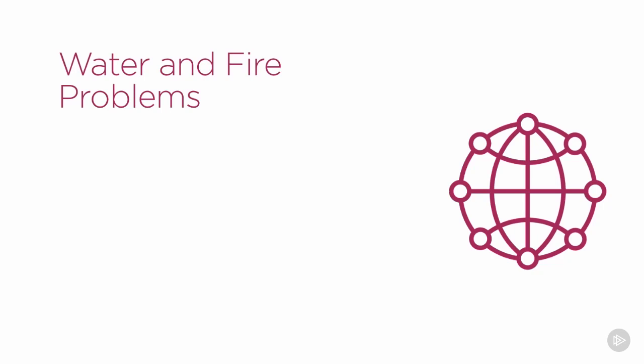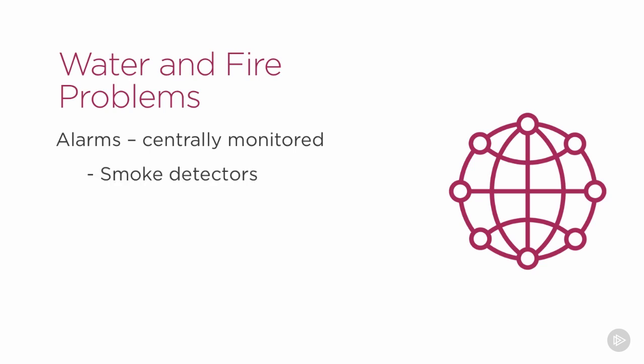But some of the problems we face, of course, are water and fire. This is where we should have smoke detectors and fire alarms throughout the building. We should have water detectors in places like, obviously, even underneath raised floors. And these alarms should be centrally monitored and linked together. So if there's an alarm in one part of the building, the rest of the building is notified.